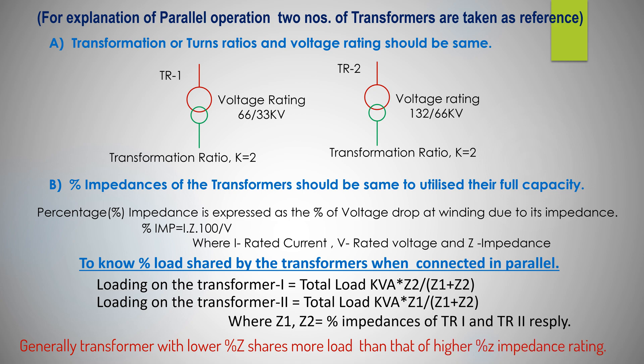If the percentage impedance or ratio of resistance to reactance are not same, there will be no circulating current, but the division of load between the transformers or among the transformers when applied will no longer be proportional to their KVA or MVA ratings. Hence, the capacity of the transformer cannot be fully utilized.